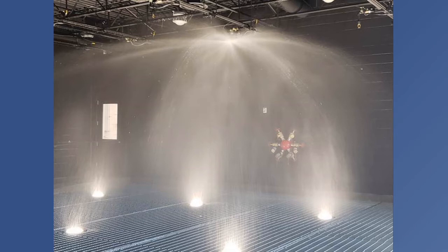Okay, so with the standard spray pendant, we're really focused on what's below. Is there a requirement for when we're getting a listing under UL 1626? Is there a requirement for how far down from the ceiling that spray pattern needs to hit the wall? Yeah, with residential sprinklers, it's going to be 28 inches down from the ceiling, regardless of what the coverage area is for the sprinkler. So once you move out into those 20 by 20 spray patterns for some of the larger pendants and larger coverage areas, you still have to be able to wet the wall on the side of the room 28 inches down from the ceiling with a residential, regardless of what the spray pattern is.